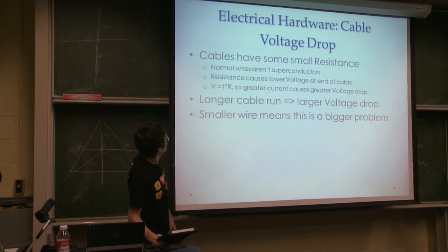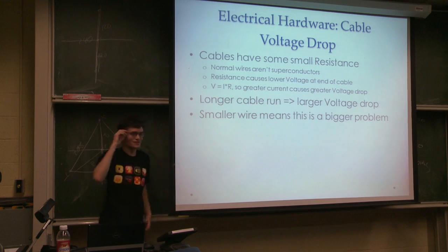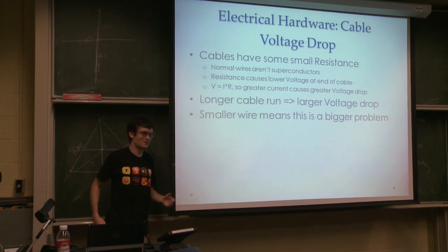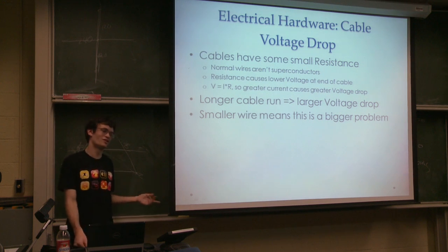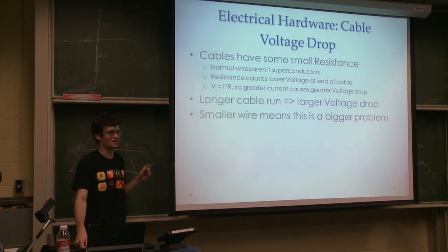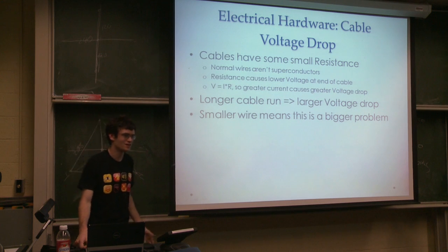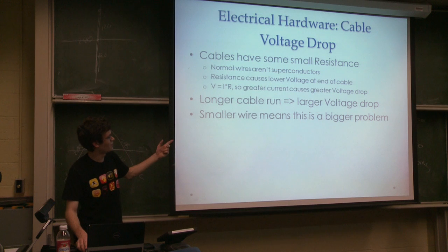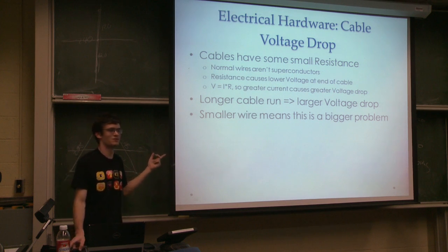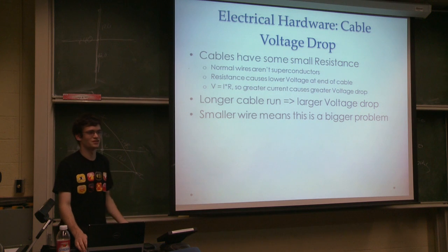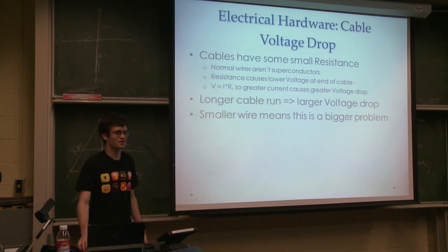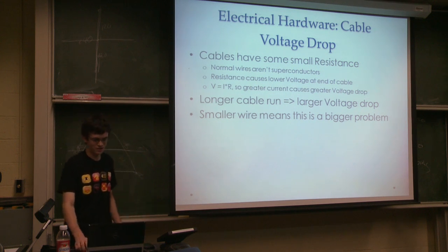Analogies. So the important thing is, if you think you're pushing a certain voltage across a cable for your math and it's really long, it will actually be slightly different, and you want to take account of this fact if you're doing ME work. Smaller wire is a bigger problem because you already have lower current limits. So when you're losing voltage, it has essentially a greater effect.